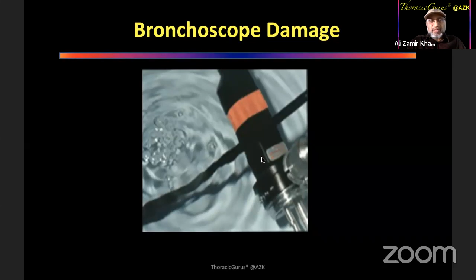Now, the problem with this damage is it will cause water to seep into the sheath, and more importantly, it will cause bacteria to seep into the sheath, which you cannot clean off. So there is a high risk of infection, cross-infection from one patient to another when you have damage to the bronchoscope. So this has to go back to the manufacturers for repair, and they have to resheath it. So quite an expensive procedure.